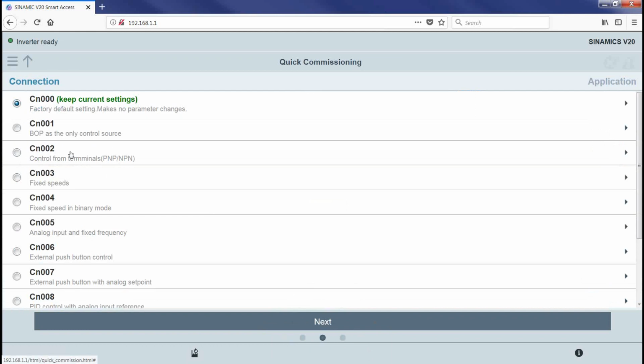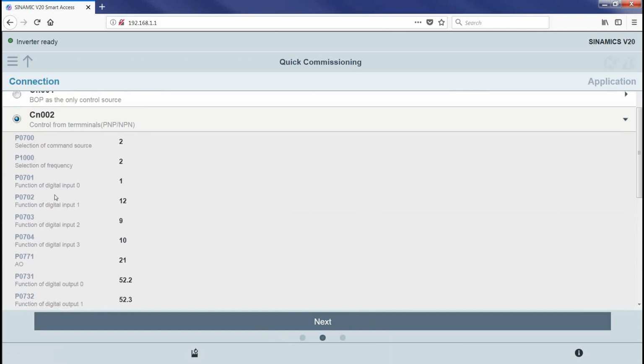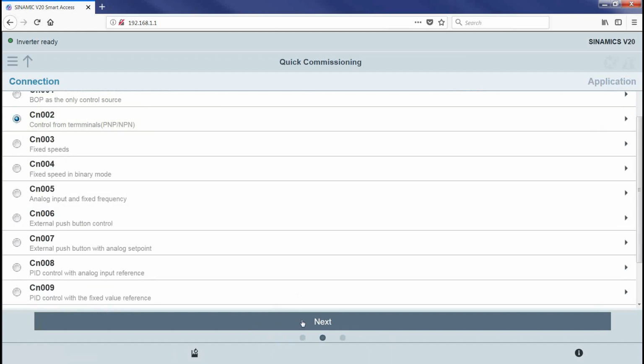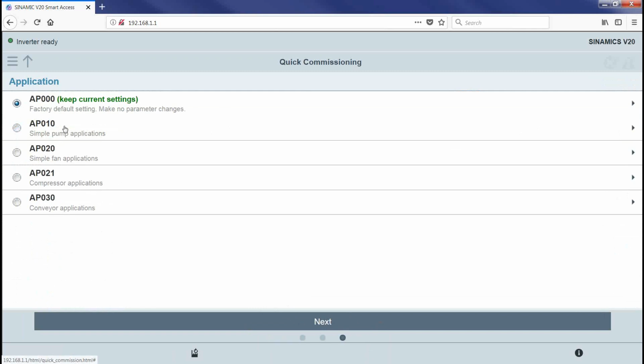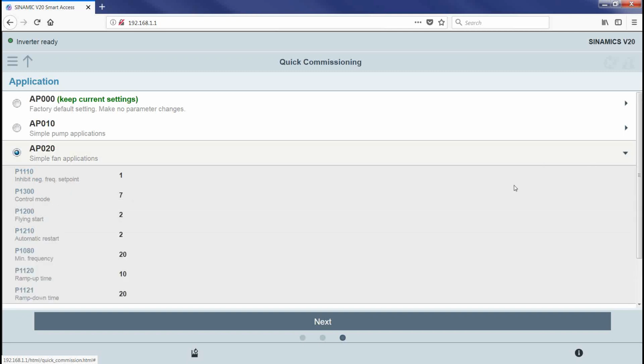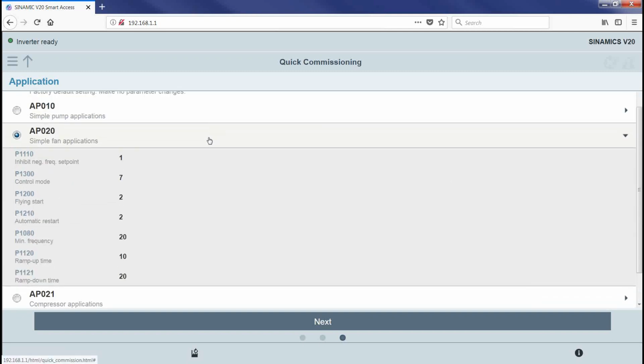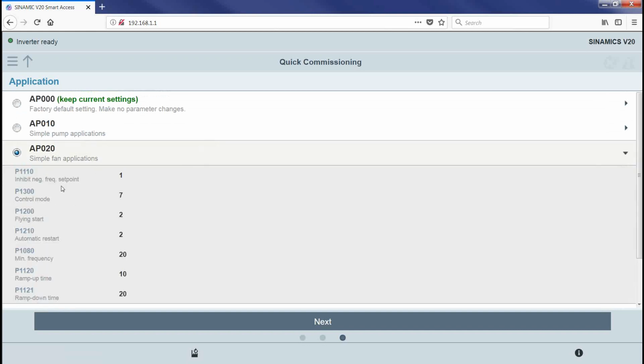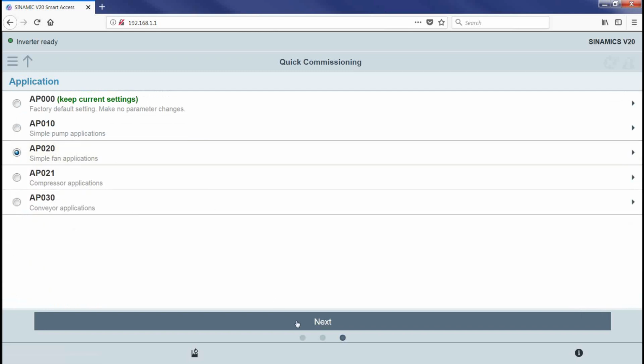All right, again, we're going to pick Cn002 because I've got some push buttons tied to this drive, a selector switch actually. So I'm going to select PNP and NPN. If you click this right arrow, this shows you what parameters are going to be set based on this. So Cn002, make sure it's selected. Next. Here's our application macro. Again, I'm going to do an AP20. If you click the arrow, it's going to show you what these parameters are set up. So notice we got a negative frequency set point inhibit, so it can't roll backwards, if you will. Or the drive can't command the motor to run backwards.